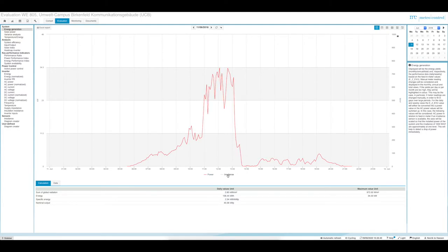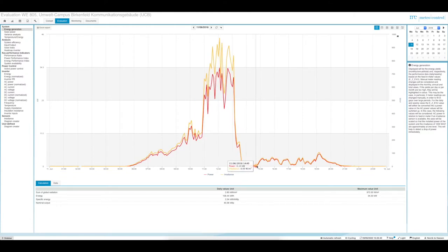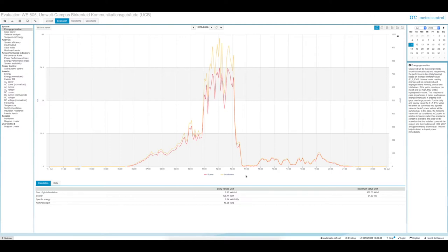If you also have the irradiance data, you can see there's a significant drop of the irradiance due to heavy clouds, heavy rains, and thunderstorms. Then you can understand why the power generation from 1:45 until about quarter to 3 PM has been close to zero — there was no sunshine, no irradiance. That's the reason why you should always have access to irradiance data, measured on site by a pyranometer or a crystalline cell sensor, to evaluate the power generation of the PV system.